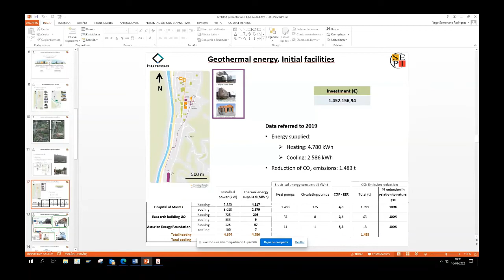Now we have the scheme of how the initial facilities work. We have 4 different pumps in the shaft with a safety water level at 35 meters. We have water at a temperature of 23 degrees, and it goes to a heat exchanger in the building of each client. We have a closed circuit, for example the circuit to the hospital of Mieres, changing the temperature from 20 to 15, and then the 3 heat pumps working for the hospital in the same building.